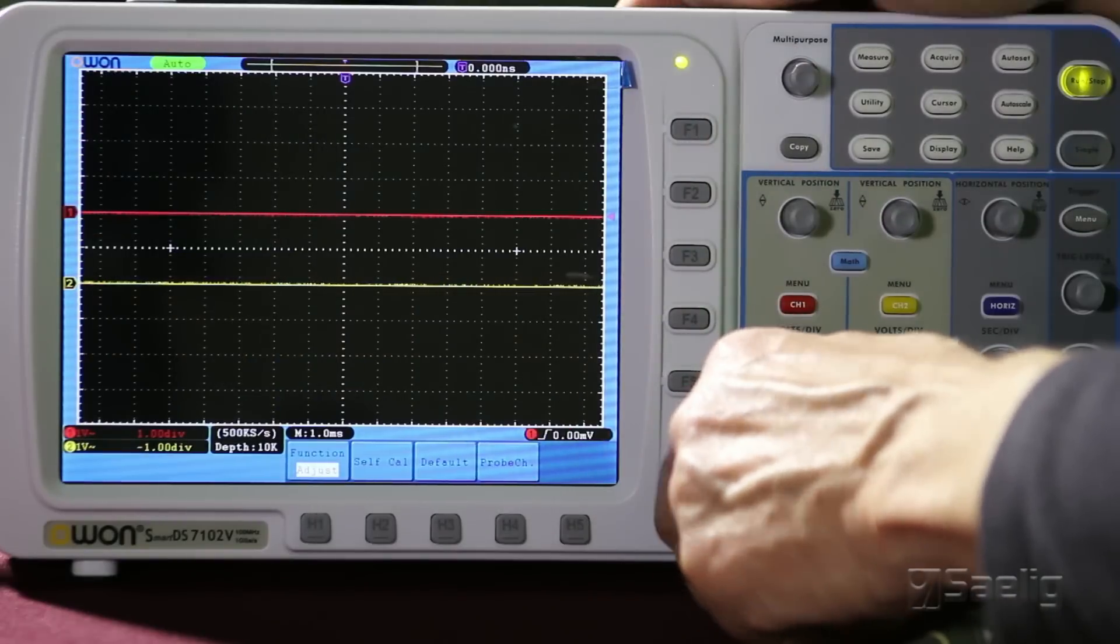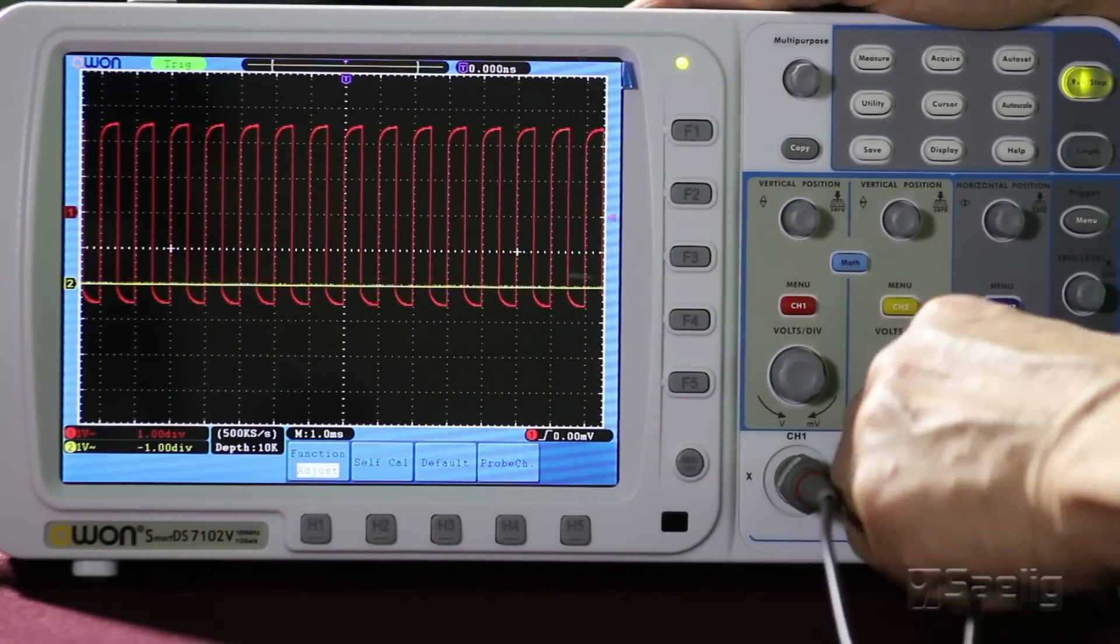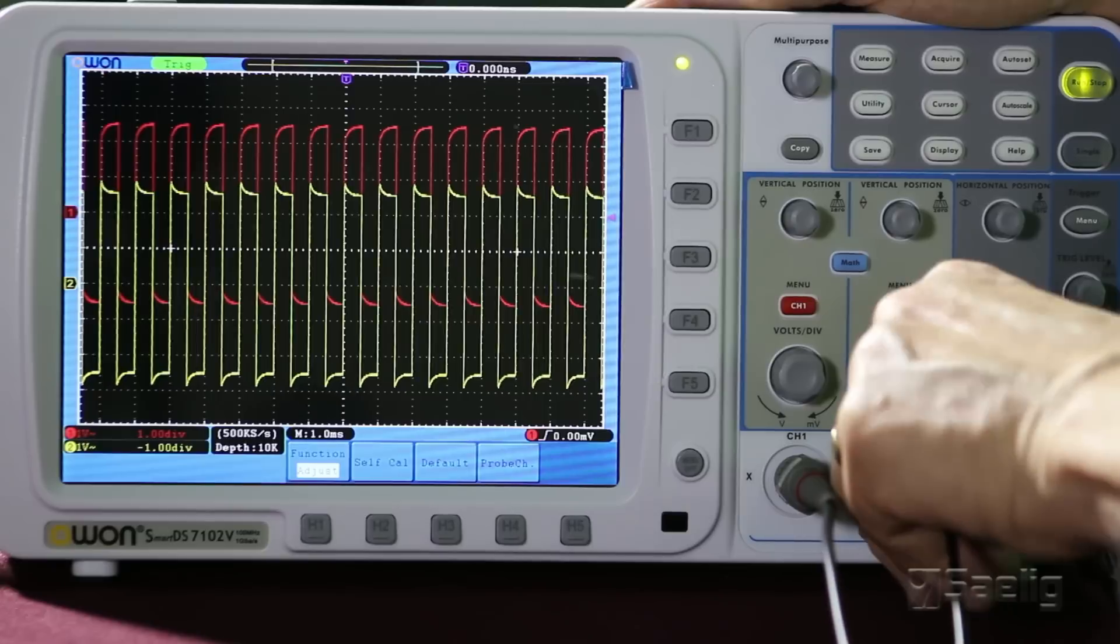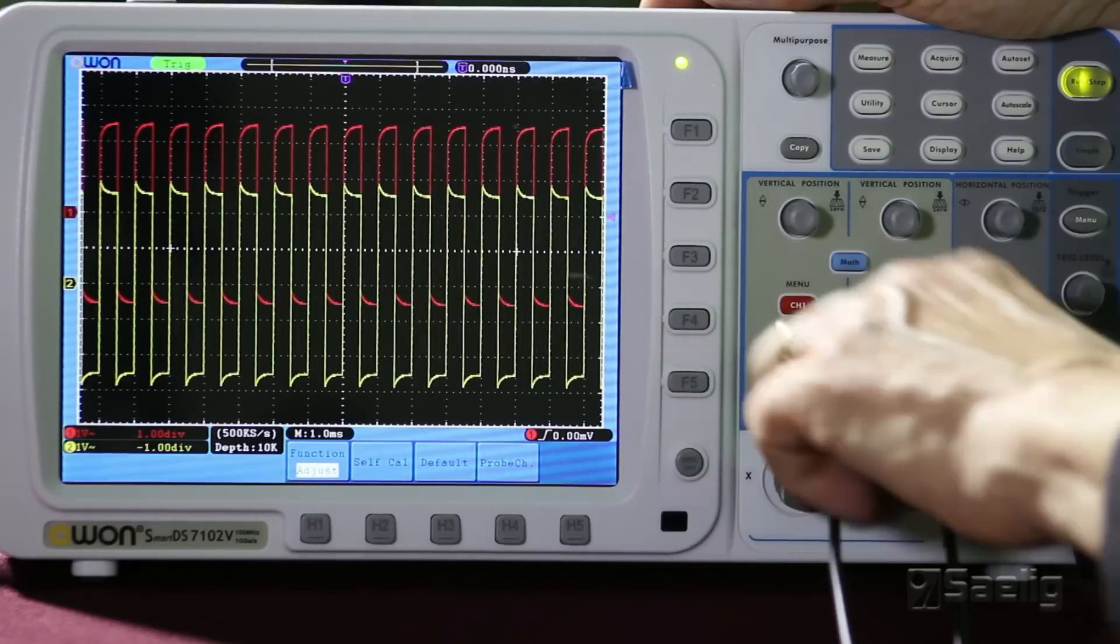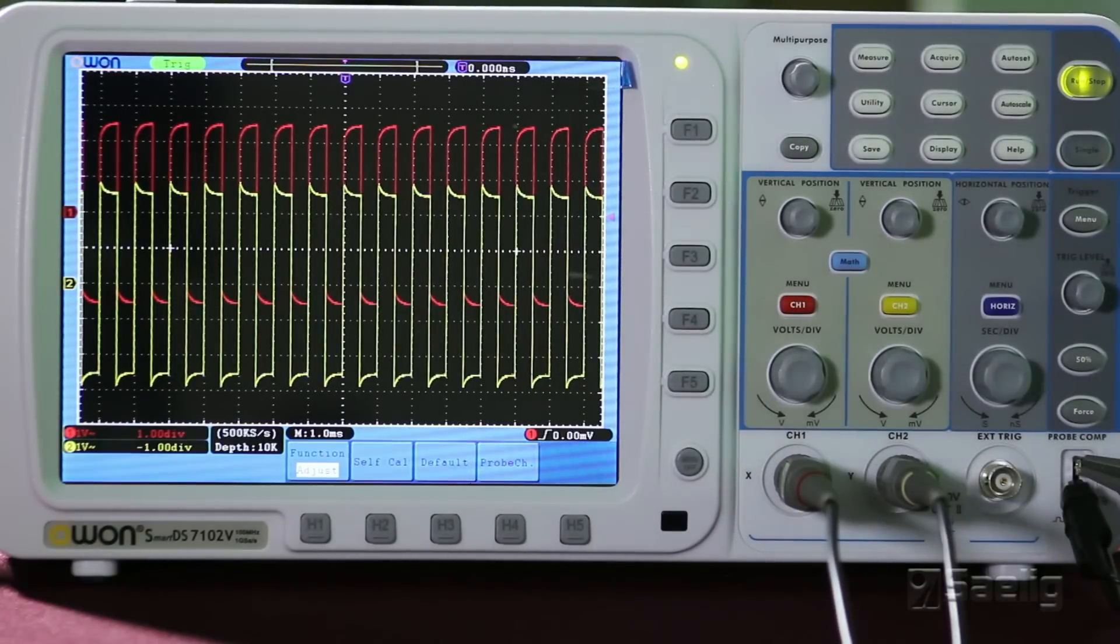So I would have a fairly high level of confidence in this scope. So let's hook up some probes and just see what we get for some signals. We're using the calibrator output right here on the front of the scope, which puts out some kind of a square wave at a certain frequency and a certain voltage, peak to peak level.